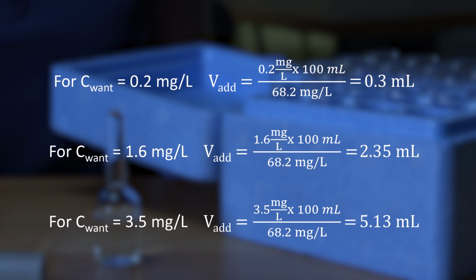understanding of these procedures. If your primacy agency requests or your water system decides to perform a performance evaluation, a certified standard solution of chlorine having an unknown concentration would be purchased. The performance evaluation procedure describes the amount of the certified standard to be added to a known volume of purified water. Then, the measurement of the unknown concentration can be checked for individual analysts by reporting the results to the certified solution provider for comparison to the allowable range.